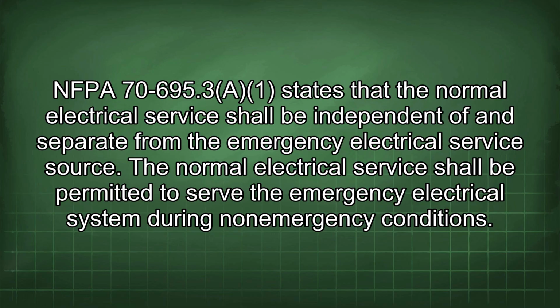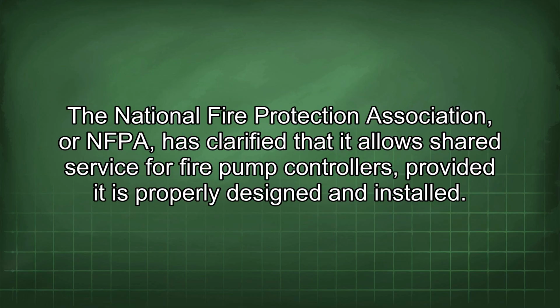NFPA 70-695.3(A) states that the normal electrical service shall be independent of and separate from the emergency electrical service source. The normal electrical service shall be permitted to serve the emergency electrical system during non-emergency conditions. The National Fire Protection Association, or NFPA, has clarified that it allows shared service for fire pump controllers, provided it is properly designed and installed.